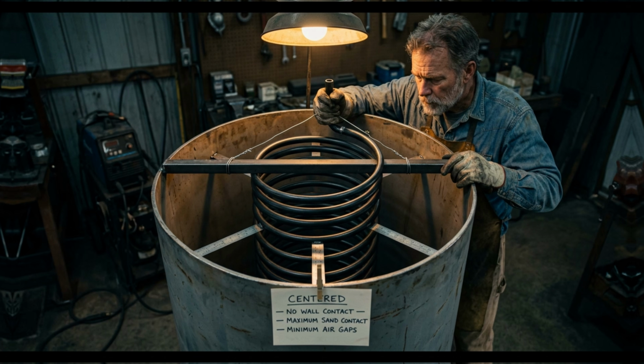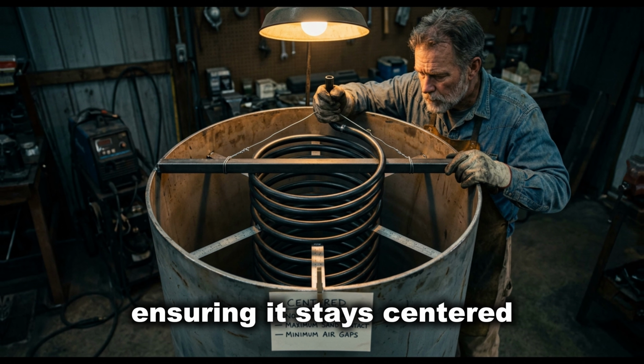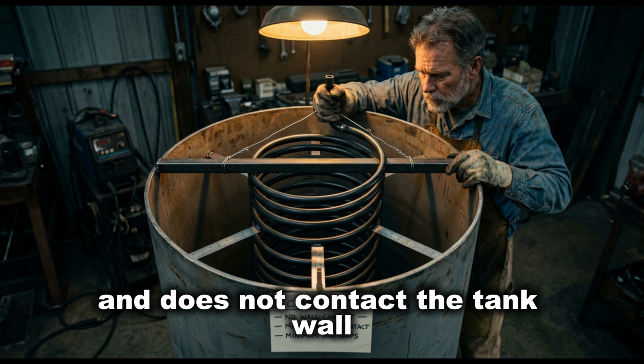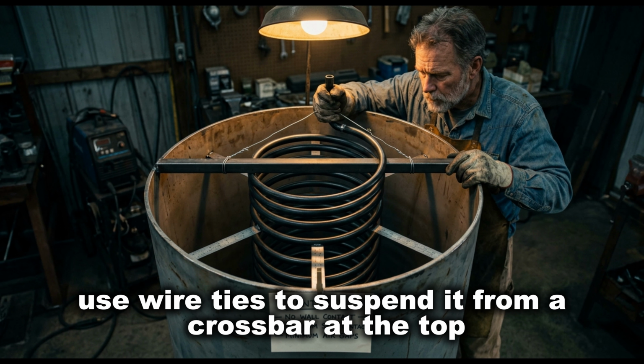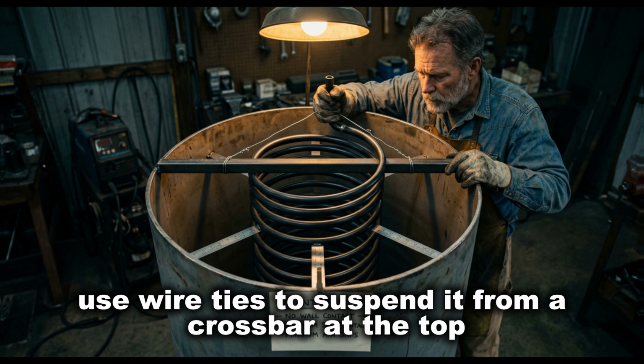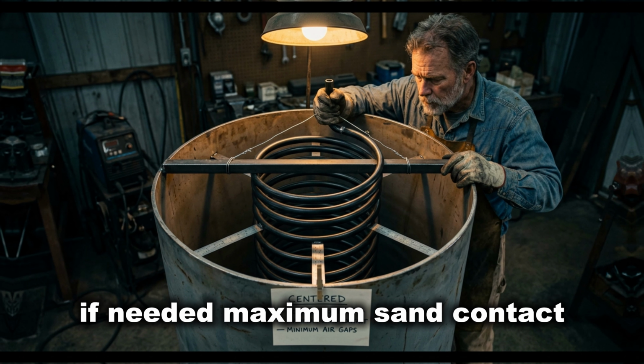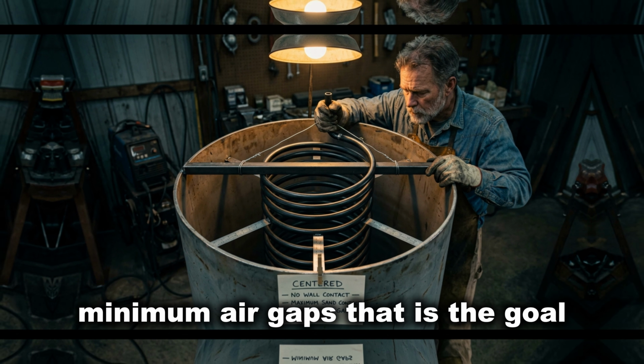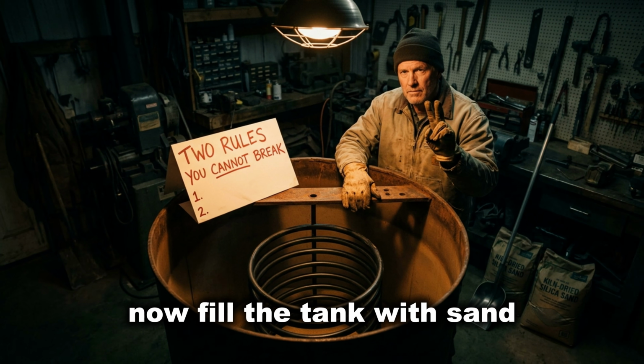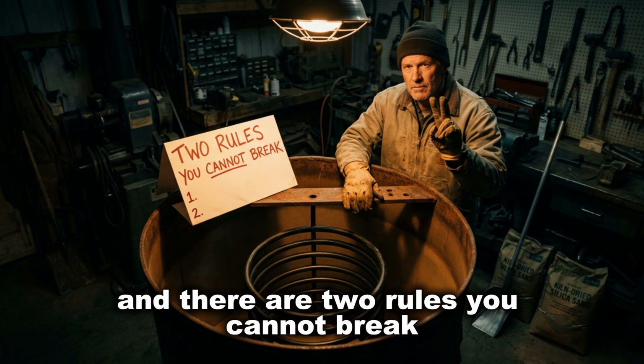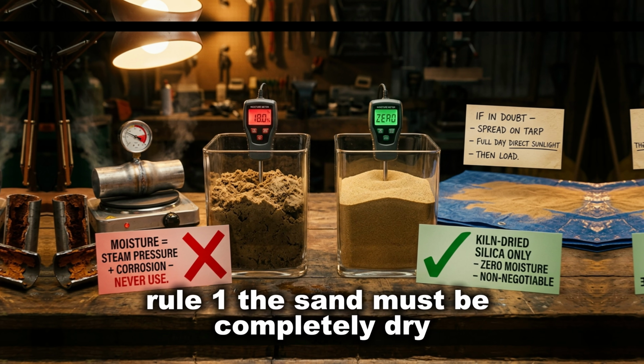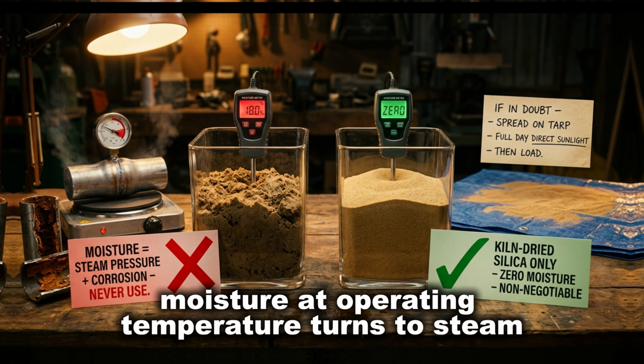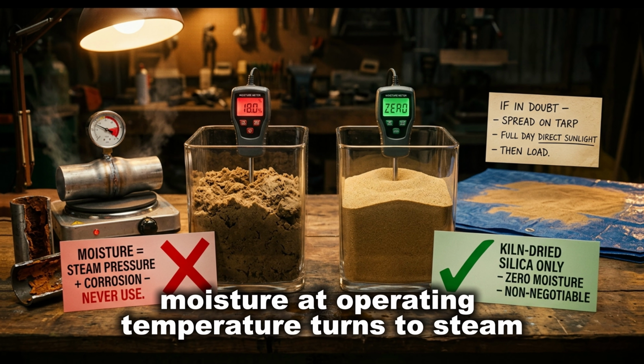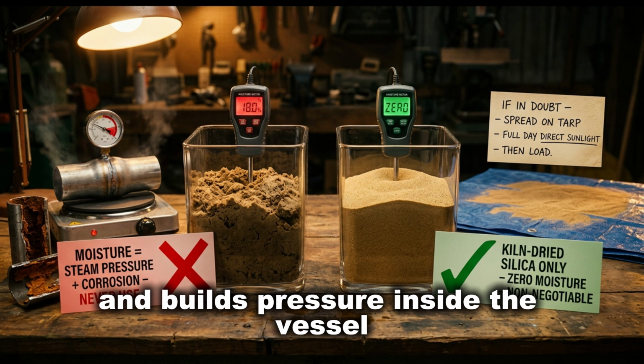Position the coil. Lower it carefully into the tank, ensuring it stays centered and does not contact the tank wall. Use wire ties to suspend it from a crossbar at the top if needed. Maximum sand contact, minimum air gaps. That is the goal. Now fill the tank with sand, and there are 2 rules you cannot break. Rule 1. The sand must be completely dry. Moisture at operating temperature turns to steam and builds pressure inside the vessel.